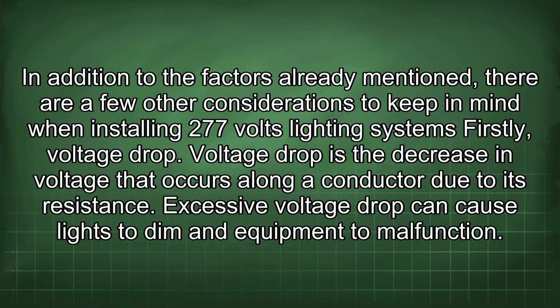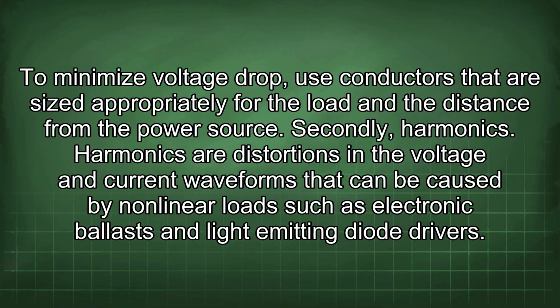In addition to the factors already mentioned, there are a few other considerations to keep in mind when installing 277 volts lighting systems. Firstly, voltage drop. Voltage drop is the decrease in voltage that occurs along a conductor due to its resistance. Excessive voltage drop can cause lights to dim and equipment to malfunction. To minimize voltage drop, use conductors that are sized appropriately for the load and the distance from the power source.